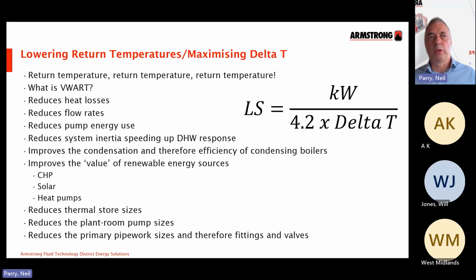And that means you kind of lead yourself down a path where you have to keep a lot of circulation going around that system, because you don't want that water to cool. If you do, there's so much volume in that system that you have to purge through your terminal units before you can actually get the output that you need. So by lowering the required flow rate, we reduce the pipe sizes, we reduce the volume on the primary system, and we speed up response times for anything, whether it's cooling, heating or domestic hot water. It becomes more critical, of course, when we look at domestic hot water response times. But it's one of the key aspects that we need to focus on.